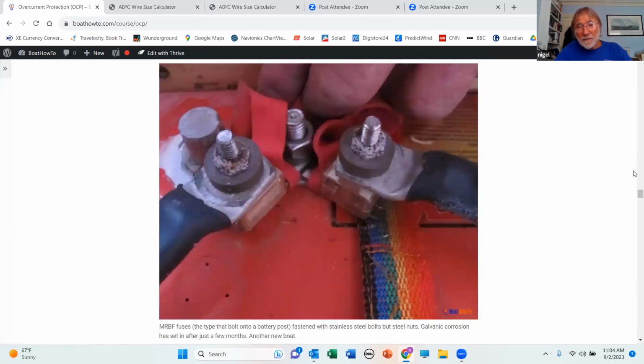Now, I mentioned the MRBF fuses earlier. These are the ones that bolt to the top of a battery post, and that's what we can see here. They're square fuses, and the battery connection is on the bottom, and the terminal is on the top going out to the conductor. And you can get these fuses rated up to maybe as much as 500 amps. However, the AIC rating on these fuses, off the top of my head, I think is 3,000 amps. So it's too low for a large lead acid battery bank, and it's way too low for a lithium ion battery bank. So these are good for smaller lead acid battery banks, but when you get into big banks, they're not appropriate, unfortunately, because otherwise they're great.